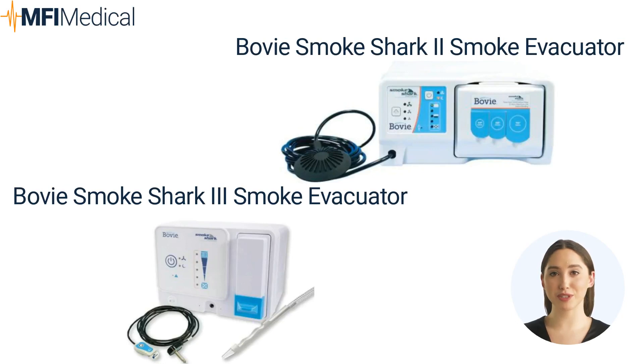The Bovie Smoke Shark 2 is a specialized device that reduces the risk of exposure to harmful smoke and aerosols produced during surgical procedures involving electrosurgery, lasers, and harmonic scalpels. These smoke plumes can contain viruses, carbon monoxide, and other dangerous substances. Equipped with a powerful and quiet vacuum motor, the Smoke Shark 2 efficiently removes surgical smoke from the operation site, passing it through a set of filters in the SF35 filter. The system utilizes a single disposable filter, making installation and replacement easier.